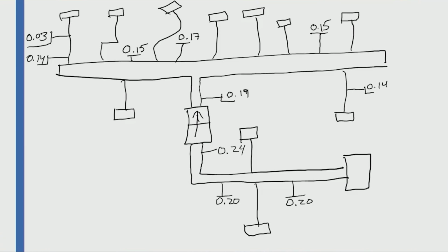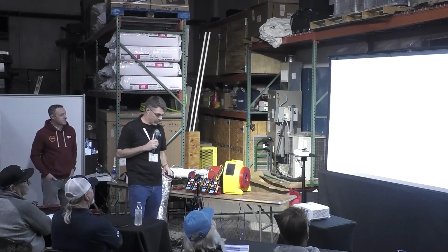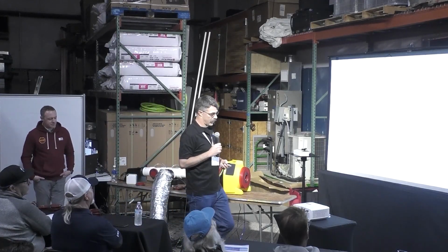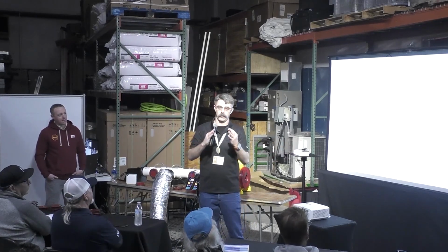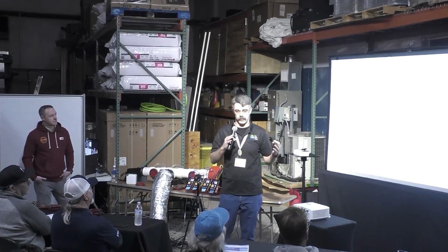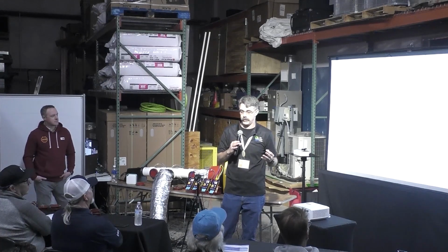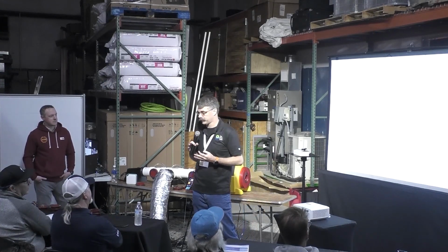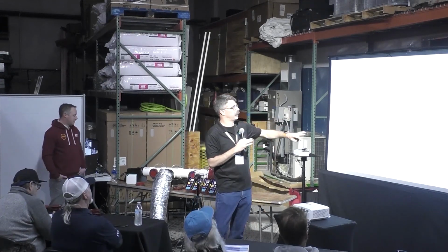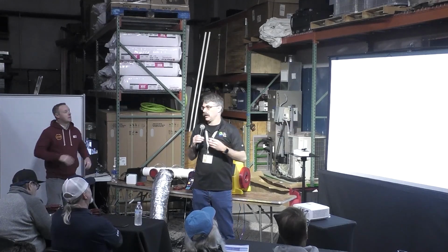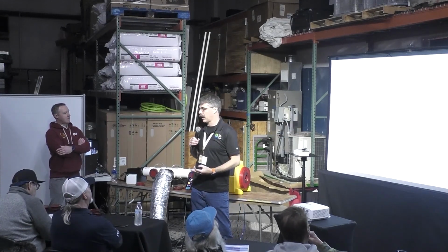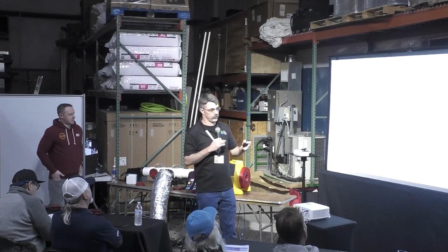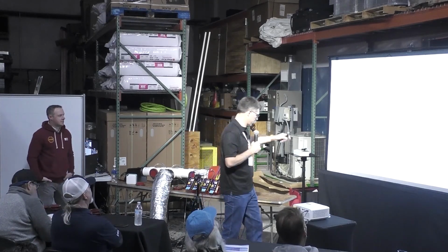Finding those restrictions matters, because when you have airflow problems, we need to separate complete system airflow problems from airflow problems in one room, or maybe in one or two spaces.